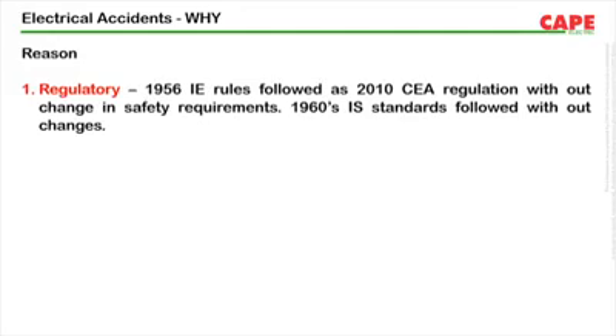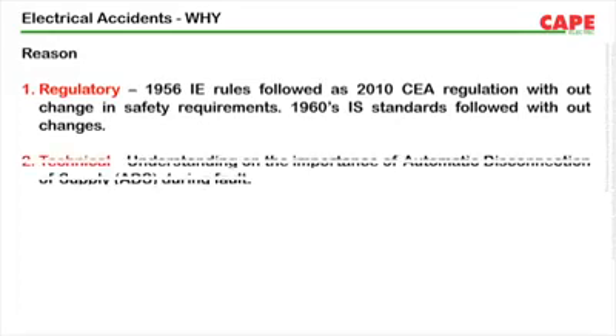There is no problem in using the rule because the basics of electrical safety didn't change. But the actual problem is that during these last 50-60 years, we misinterpreted these rules a lot. As a result, we lost safety. I will explain a few examples later. The second reason is technical. Understanding the importance of automatic disconnection of supply during a fault is not understood well. We believe the protective device such as MCB and fuse installed in our line will work, but we do not follow the fault loop calculations to find out whether this device will do its intended job or not.